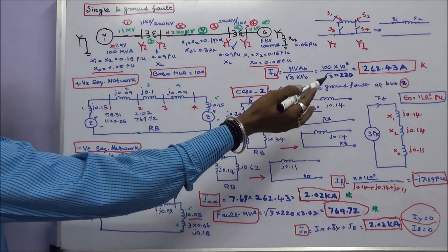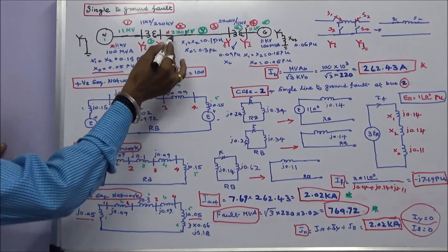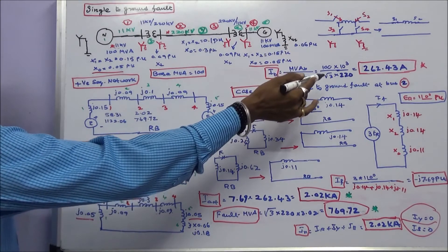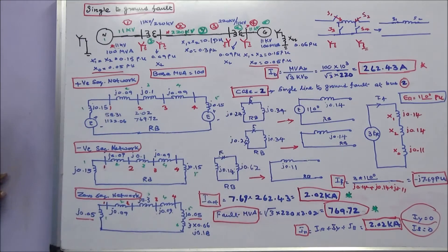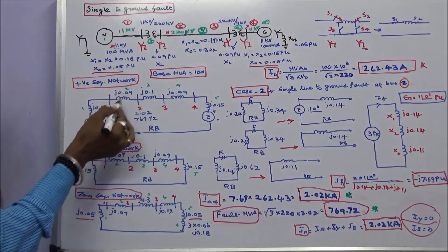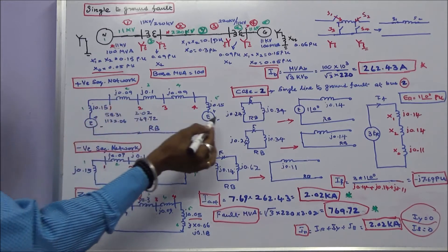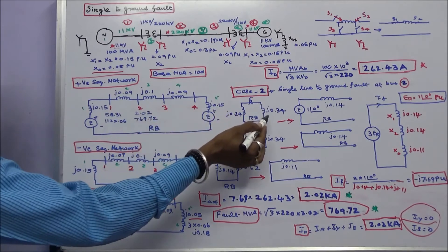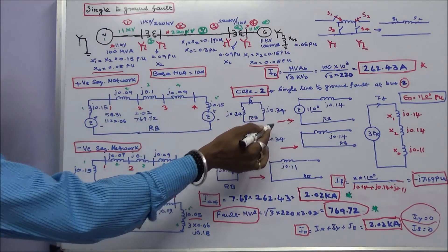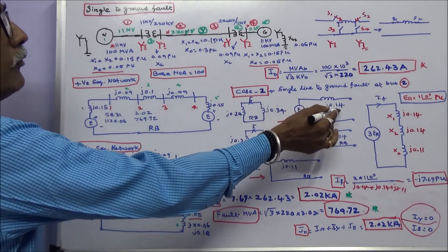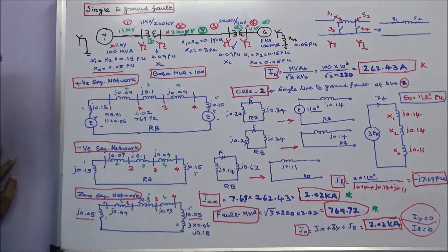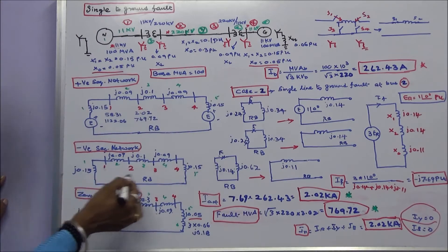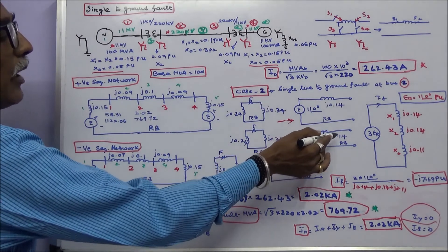Case 2: single line-to-ground fault at bus 2. The voltage is 220 kV. Base current equals 100 times 10³ divided by root 3 times 220, giving 262.43 amps. With fault at this point, the reactance on one side is j0.15 plus j0.09, equaling j0.24. The other side reactance is j0.1 plus j0.09 plus j0.15, equaling j0.34. The positive sequence equivalent Thevenin reactance is j0.14. Prefault voltage is 1.0. Removing sources gives negative sequence network with equivalent Thevenin reactance j0.14.